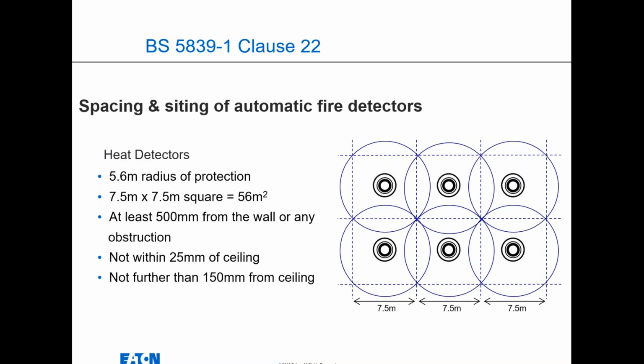With heat detectors, the radius reduces, so you end up with a smaller protection space because they are working on heat rather than smoke, and heat is harder to pick up quickly. So they have more condensed detection in the space, similar to the smokes, but they shouldn't be any more than 150 mil from the ceiling.